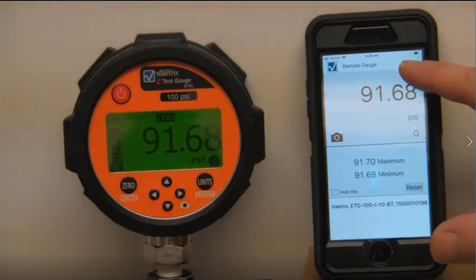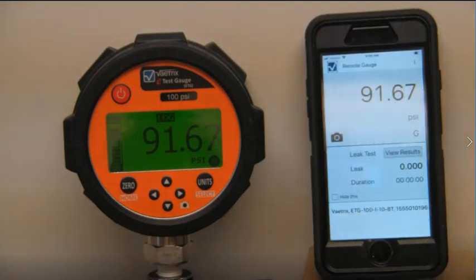Another handy feature we have is the leak test feature. So I am going to start a leak test. As you see we are counting down, we have a real-time clock in the gauge. So this is a pressure decay method. You have to run the test for at least 10 seconds to get meaningful data. We are going to run it for 20, and then I am going to review the results.